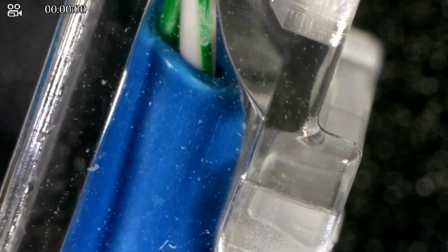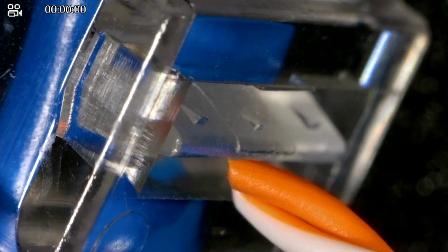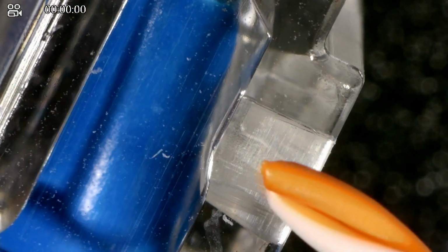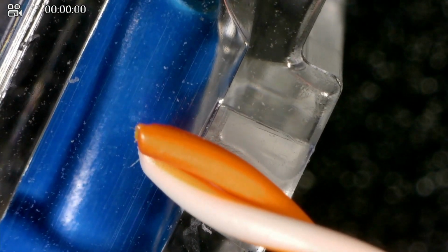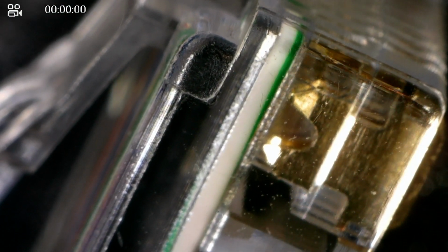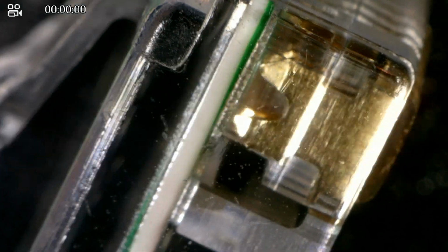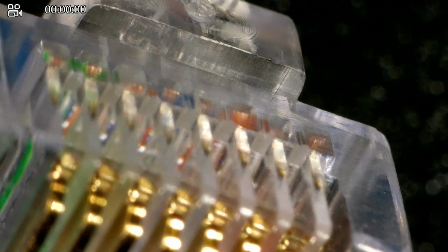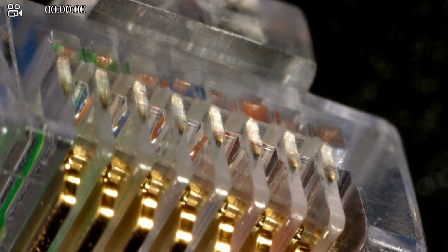When the clip comes down, here's the clip. Where's the clip? See, that's where the clip is, right here. Okay, that's the clip. That thing is going to come down and pinch the insulation in place so it stays there, and the conductors are going right up to the front. So that's good. If there are any conductors that don't go to the front, that is not good, because that means there's a chance that the connector is not going to make contact with the copper wire. Right?